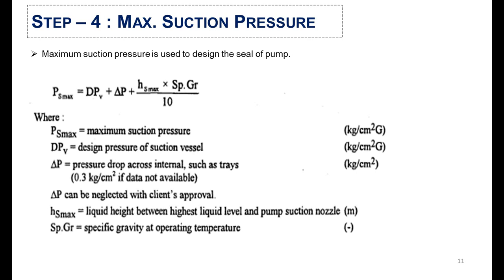In the fourth step, you will calculate the maximum suction pressure, which is used to design the pump seal. The formula states that DP is the design pressure of the suction vessel, while delta P is the pressure drop across internals such as trays — mostly used where there is a stripper or absorber — to accommodate the pressure drop across packing or trays. If data is not available, we will use 0.3 kg, and it can also be neglected with the consent of the vendor. After applying all these values, we will get the maximum suction pressure.